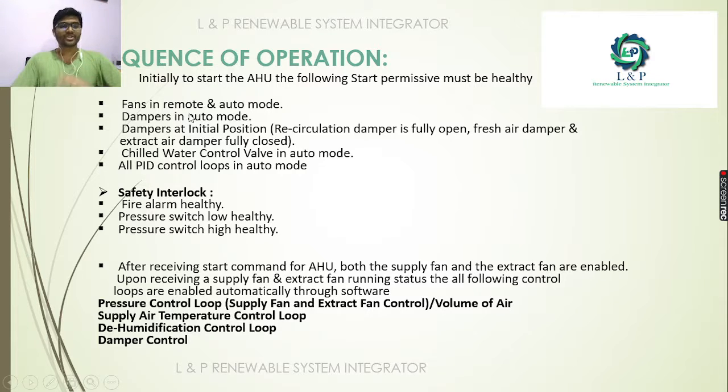Let's make a cross check whether the fan is in the remote or the auto mode and the damper in the auto mode, and whether there are some initial positions. As I told earlier, the recirculation damper is always in the fully open position, and the fresh air and the exhaust dampers should be in the closed position during the starting of the AHU operation. And most importantly, there should not be any fire signals, any low pressure alarms, or any high pressure alarms.